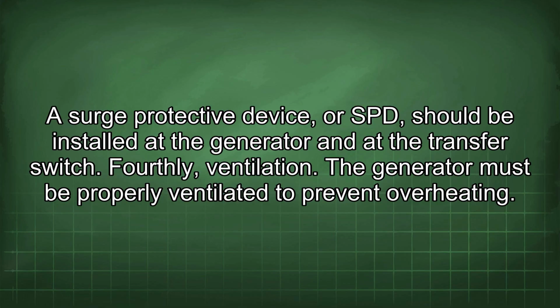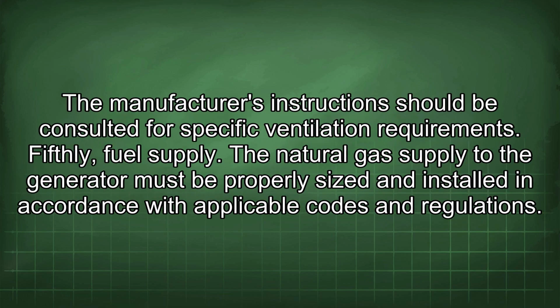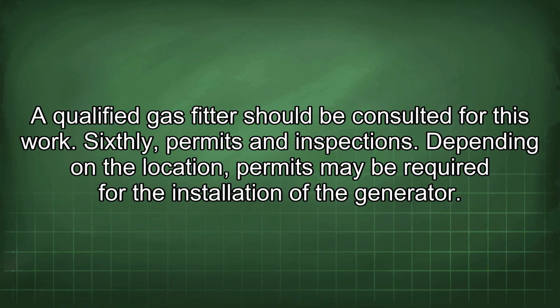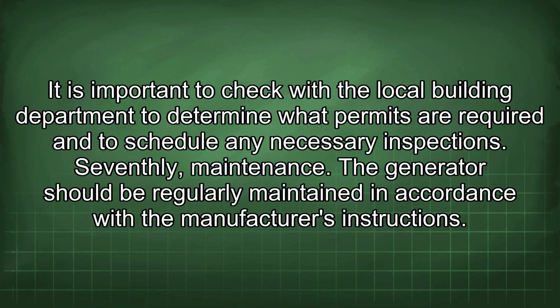Fourthly, ventilation. The generator must be properly ventilated to prevent overheating. The manufacturer's instructions should be consulted for specific ventilation requirements. Fifthly, fuel supply. The natural gas supply to the generator must be properly sized and installed in accordance with applicable codes and regulations. A qualified gas fitter should be consulted for this work. Sixthly, permits and inspections. Depending on the location, permits may be required for the installation of the generator.